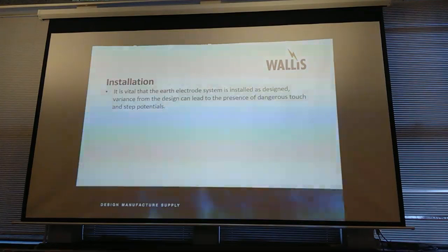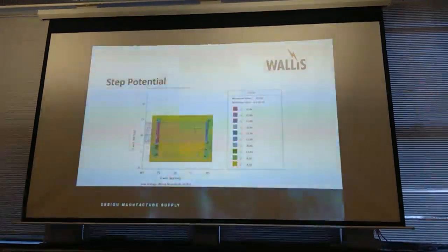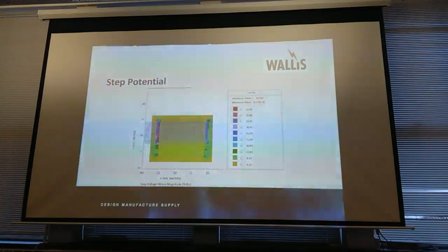Problem with that is, we've designed it, we've modelled that, so that earth rod there is usually, we put the earth rods at the corner of the earth electrode system, or the edge. And what we're trying to do there is, we're trying to drag that fault current that's sitting at the edge there, we're trying to drag it down deeper into the general mass of Earth, where it's not going to do any harm. If you start moving those rods around without actually asking the designer, you can alter all of these touch and step potential layouts. And so you can actually start causing yourself problems.